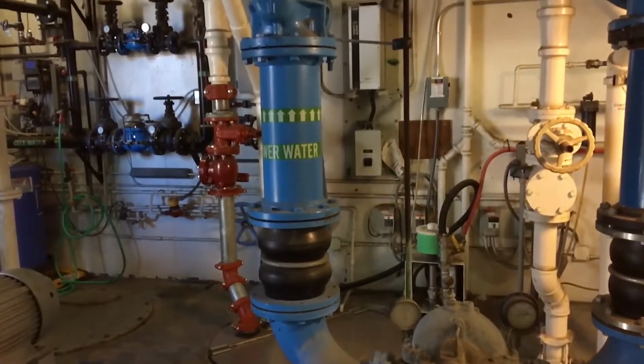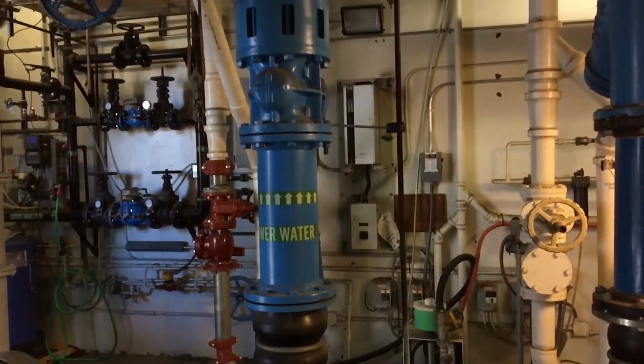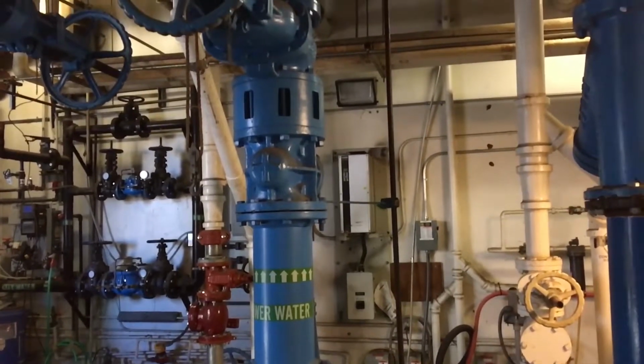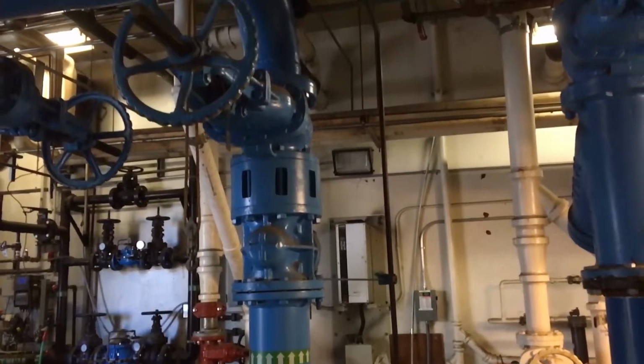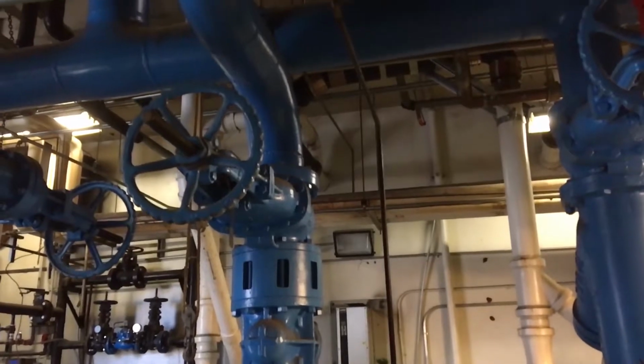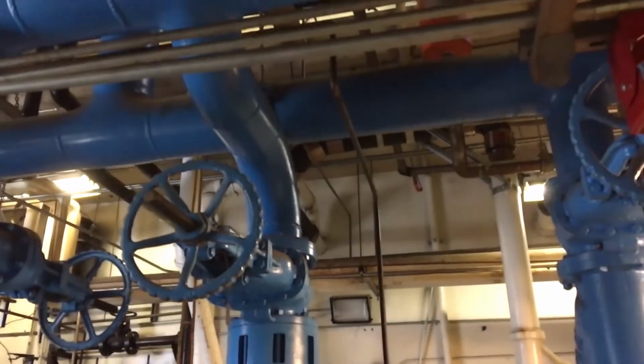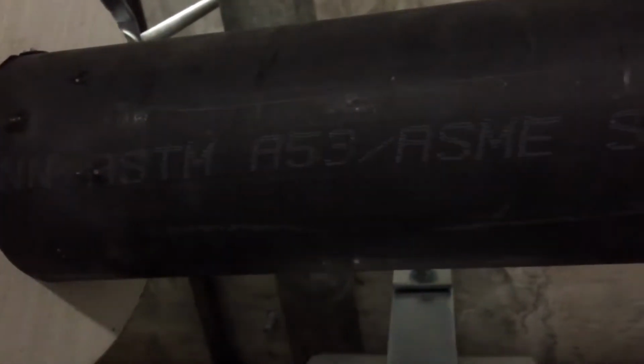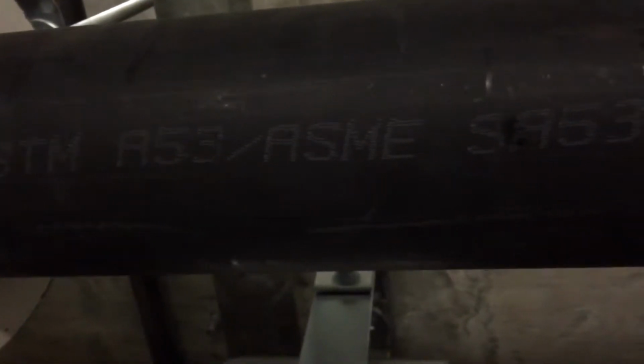After the water has been heated or chilled, it is then pumped through an air management system and then a series of pipes to distribute it into the building to be used at the terminal units in their desired locations. Steel pipe is normally used for larger sized hydronic heating and cooling piping in commercial and industrial installations. As you can see, there are markings laid out by the manufacturer to show that it is made in accordance with American Society for Testing and Materials A53.